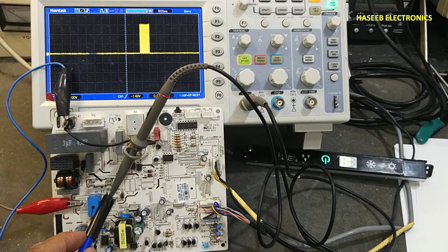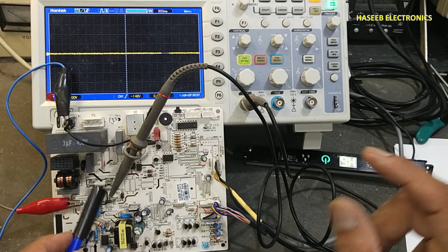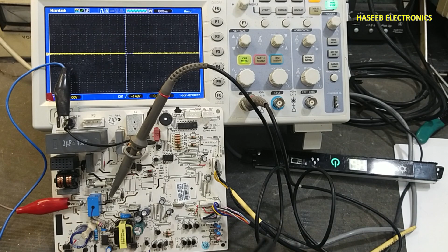It is waiting for the communication from the outdoor unit, but it is not receiving any feedback, any command, so it is trying again and again. After that, it will generate an error code for the communication. It will try multiple times with specified time intervals, and it is also giving the H6 code, that is, feedback from the indoor motor has failed.